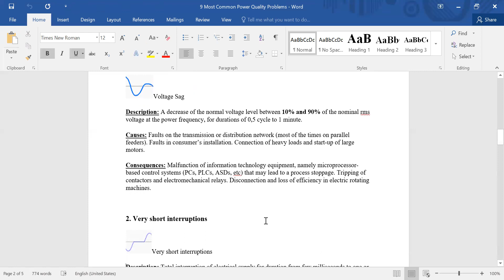Then we have very short interruptions, for short durations. Here it is shown that short interruptions are there. The description of very short interruptions is the total interruption of electrical power for a duration of a few milliseconds to 1 or 2 seconds. So the interruption will be very short for a duration of a few milliseconds to 1 or 2 seconds.